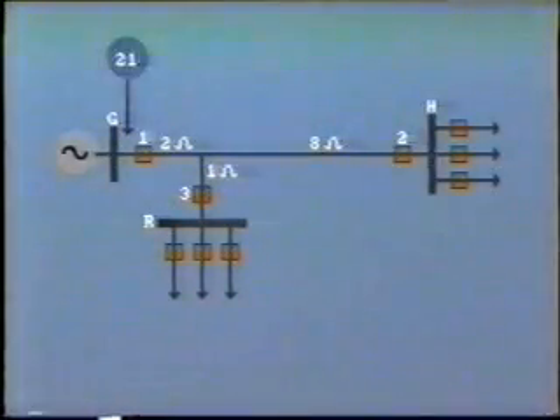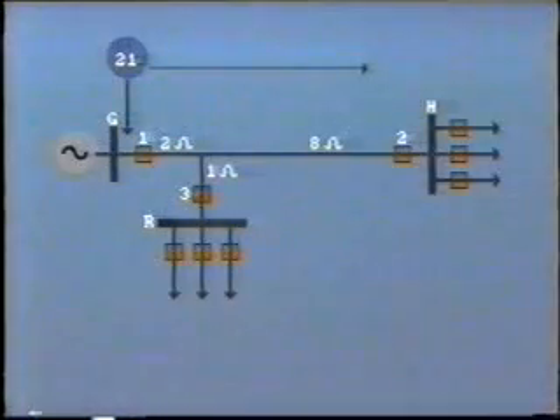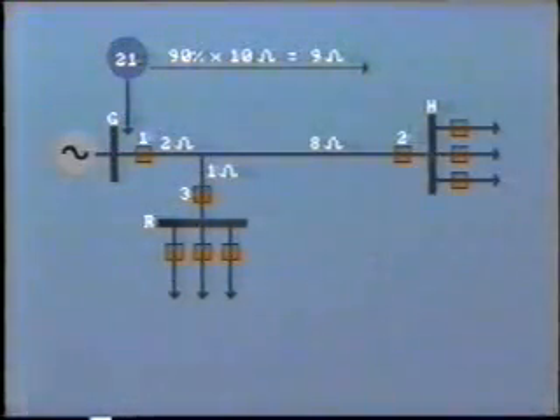Now, let us consider the distance relay, which is located at bus G. If this is to cover 90% of the transmission line, it will be set to operate when impedance falls below 90% of 10 ohms, that is 9 ohms. But look, the total impedance from bus G to bus R is only 3 ohms. So the high-speed Zone 1 protection would operate for a fault downstream of bus R, or in other words, it would reach into the feeders here.